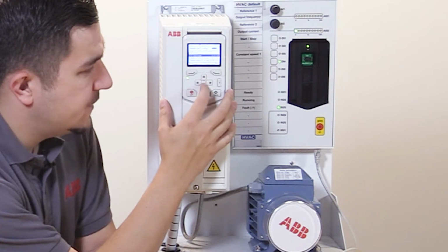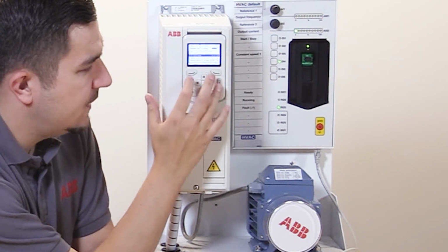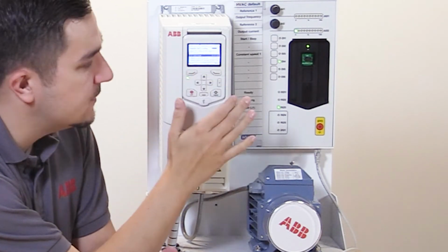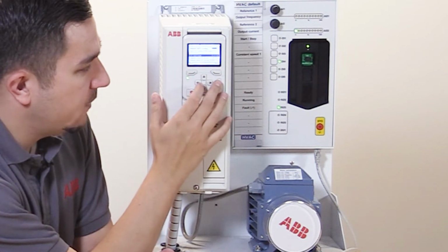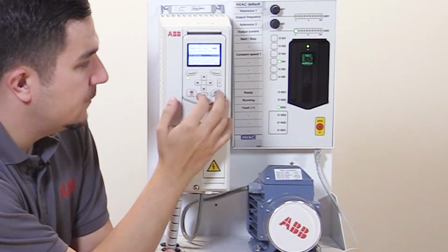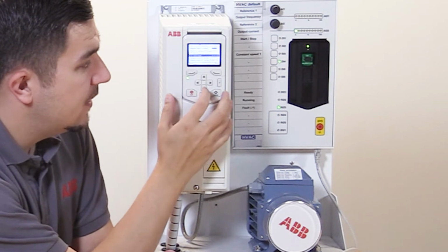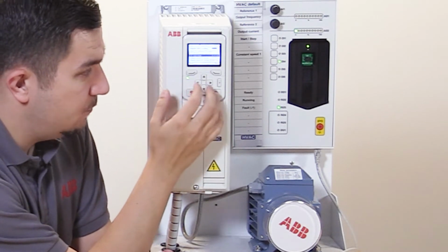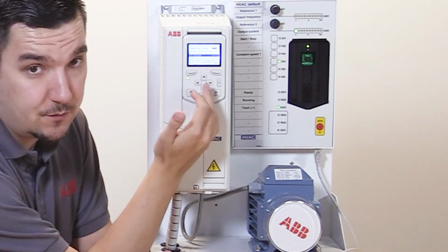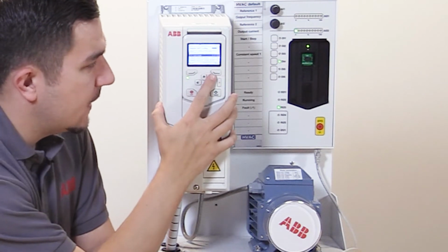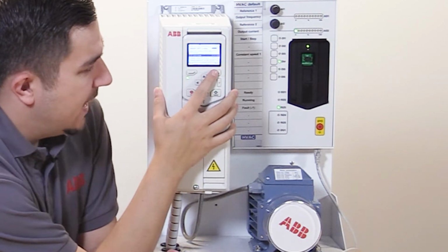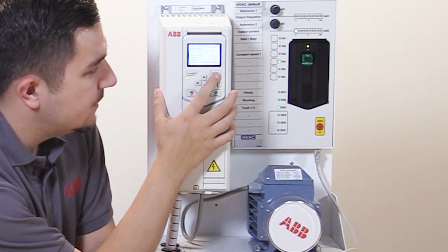We can set what our temperature range is going to be as well. In this case, I've kept it the same just to keep it simple. So our set point for analog input 1 at minimum, so at 0 volts, is 0 degrees Celsius, and our set point for analog input 1 at max is 50 degrees Celsius, just like analog input 2. And once you're happy with that, we can click on to next.